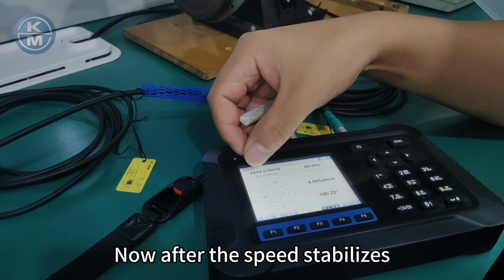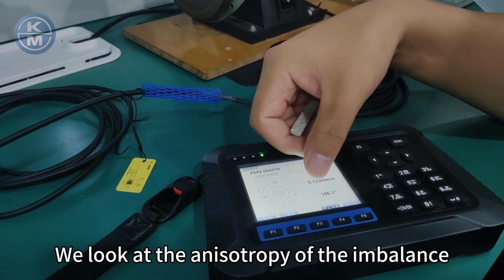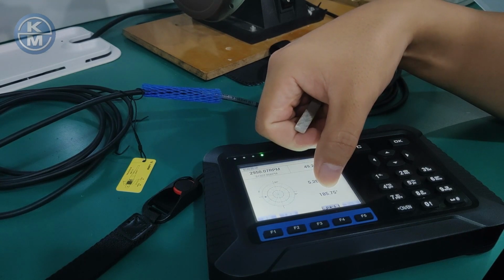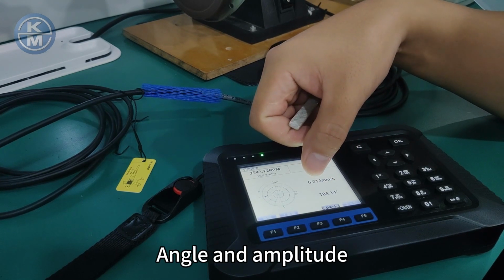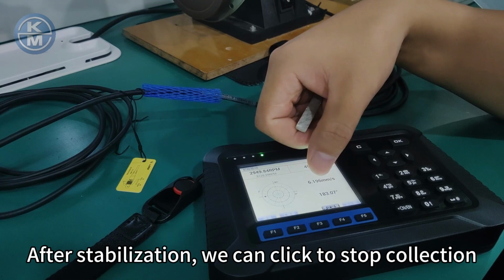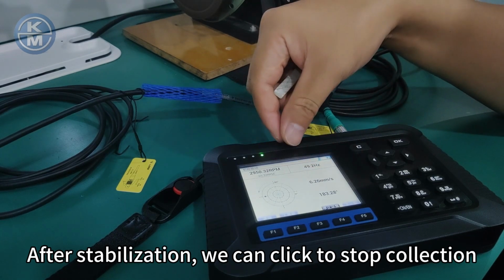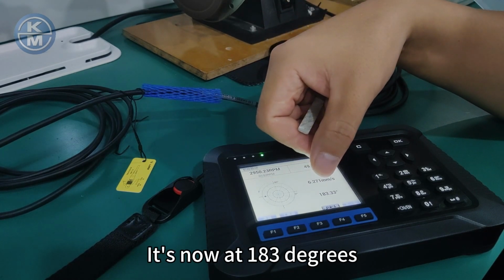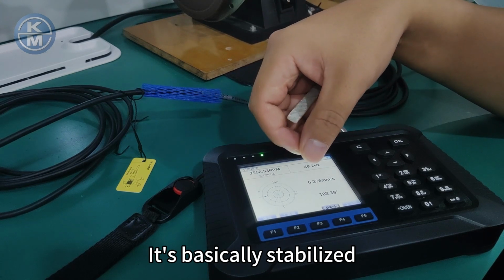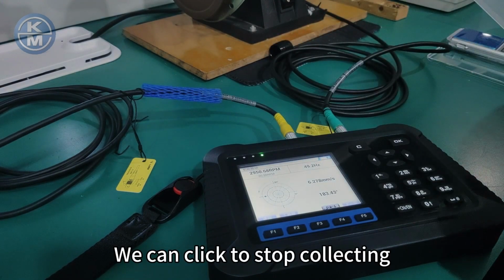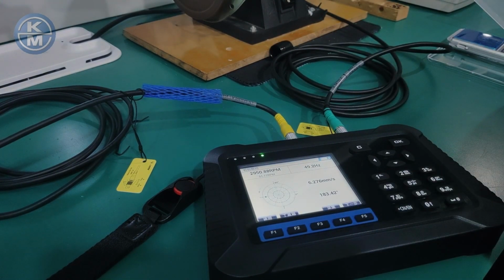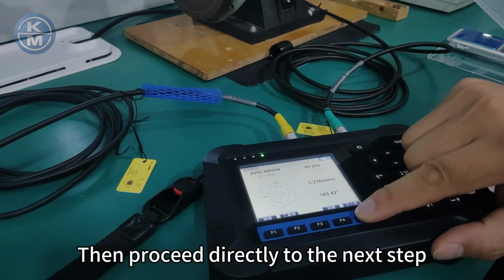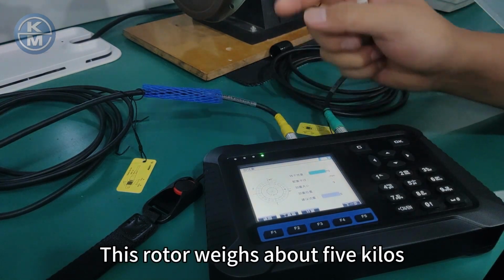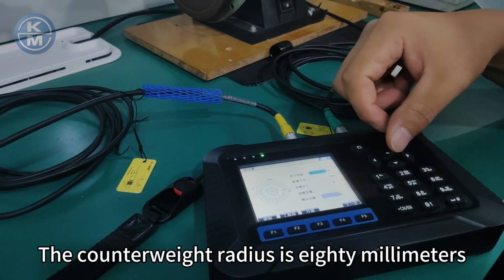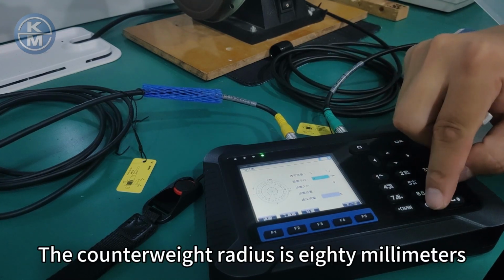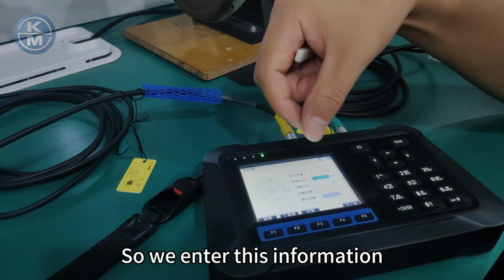Now after the speed stabilizes, we look at the angle and amplitude of the imbalance. After stabilization, we can click to stop collection. It's now at 183 degrees. It's basically stabilized. We can click to stop collecting. Then proceed directly to the next step. This rotor weighs about 5 kilos. The counterweight radius is 80 millimeters. So we enter this information.